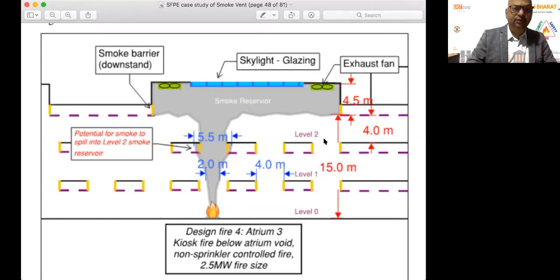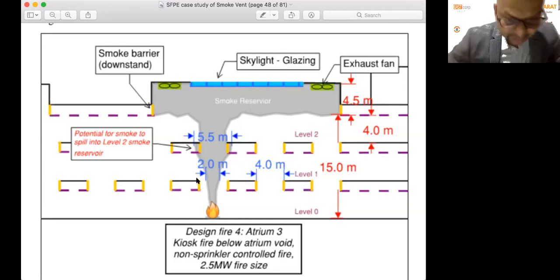So essentially, for atrium protection you need a fire detection system to monitor smoke, a sprinkler system not just on the ceiling but also in the adjoining area where there's a glass partition as part of the lobby or corridor - this is mandatory in NBC, not optional. Then you need a smoke management system using ventilation with exhaust fans, smoke barriers, fire rated doors, and fire sealing wherever needed. This is how atrium protection is essentially communicated.